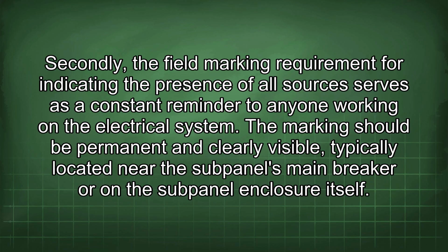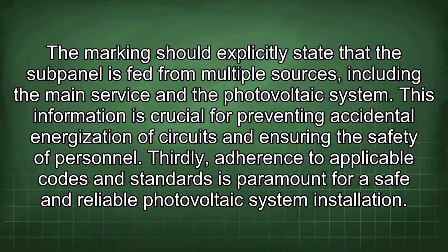Secondly, the field marking requirement for indicating the presence of all sources serves as a constant reminder to anyone working on the electrical system. The marking should be permanent and clearly visible, typically located near the subpanel's main breaker or on the subpanel enclosure itself. The marking should explicitly state that the subpanel is fed from multiple sources, including the main service and the photovoltaic system. This information is crucial for preventing accidental energization of circuits and ensuring the safety of personnel.